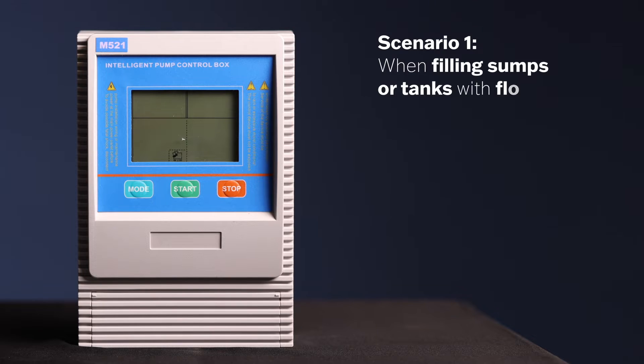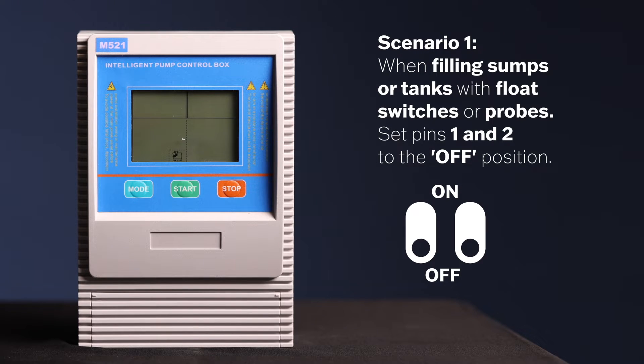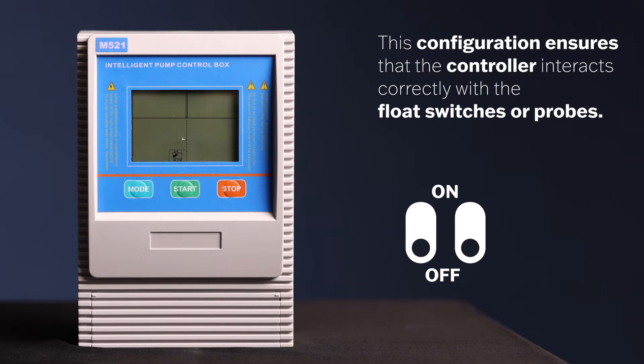Scenario 1: When filling sumps or tanks with float switches or probes, set pins 1 and 2 to the OFF position. This configuration ensures that the controller interacts correctly with the float switches or probes, allowing for effective control during the filling or emptying process.